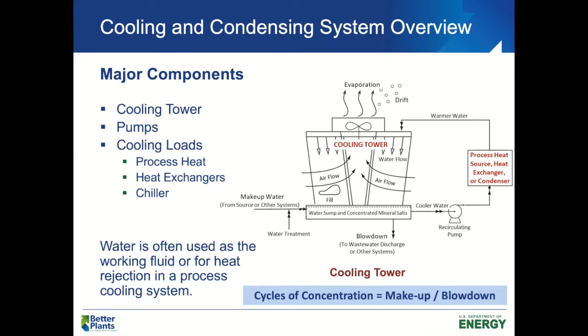So coming to opportunities, of course, the obvious first one we have is optimizing blowdown, so increasing the cycles of concentration. Some of the ways we can do this: one way is definitely improving the quality of water used. If we are able to treat the water on the front end, then we could increase the cycles of concentration proportionally. Another way to increase cycles of concentration and optimize blowdown is to put in automated blowdown controls, especially if you have manual controls being operated on a schedule. Automated blowdown controls continuously monitor the conductivity level in the tanks and blow down whenever necessary.